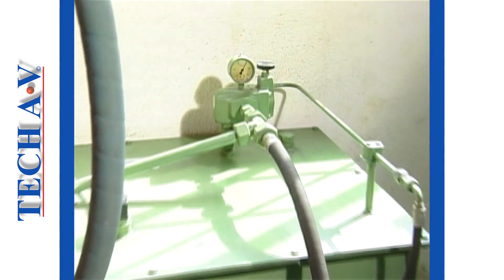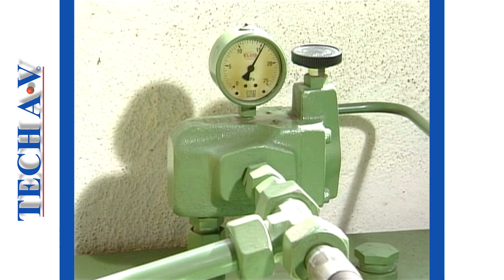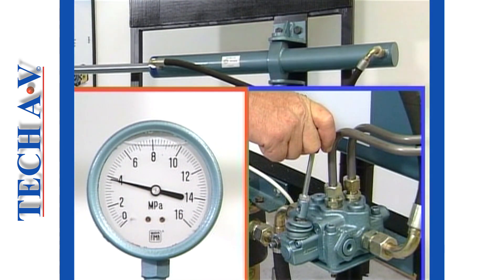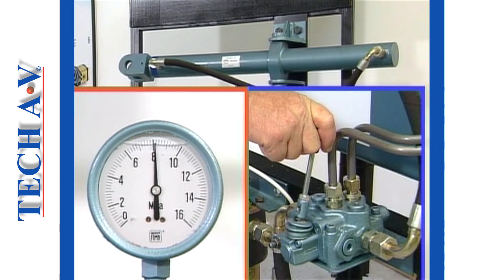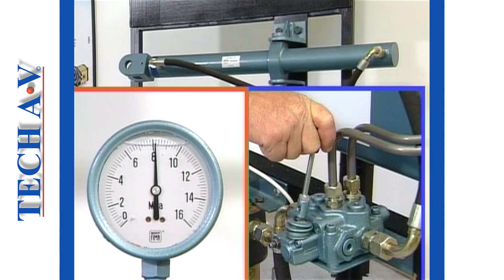Most industrial systems feature a system pressure gauge. This is a valuable aid in diagnosing problems. For example, on our demonstration model, if we hold the control valve in after the ram has reached the end of its stroke, the gauge needle will shoot up rapidly. The pressure relief valve will also be heard as it dumps the full flow of oil from the pump back into the return line. The pressure gauge reading at this time is reflecting the relief valve's setting.